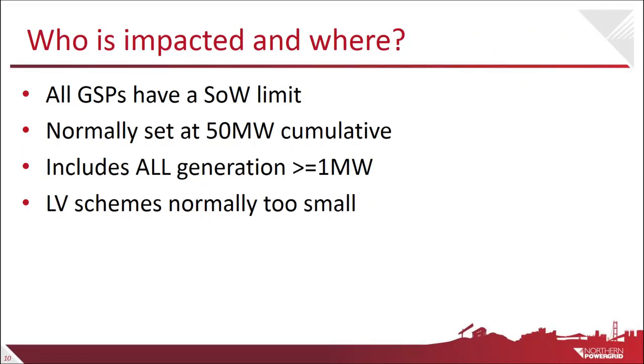This doesn't apply to all generators. All our grid supply points have a nominal statement of works threshold, typically set at 50 megawatts, although with the issues on the transmission network becoming more prevalent in Yorkshire and the North East, those thresholds are probably going to reduce — one or two sites we've already reduced by agreement. It includes all generation sites greater than a megawatt; if your overall site is less than a megawatt, you're outside the process and we don't need to ask National Grid. So generally, low voltage connected schemes are too small and aren't in the process.